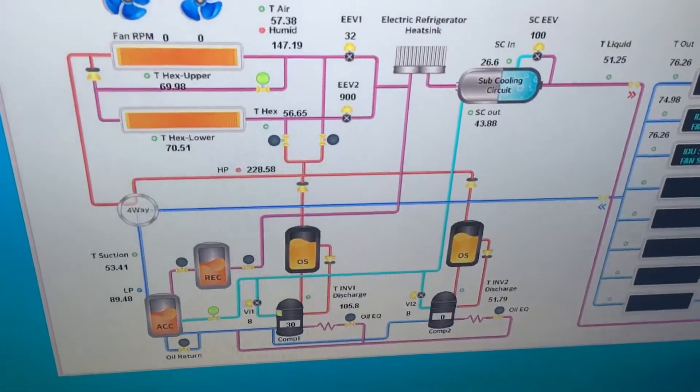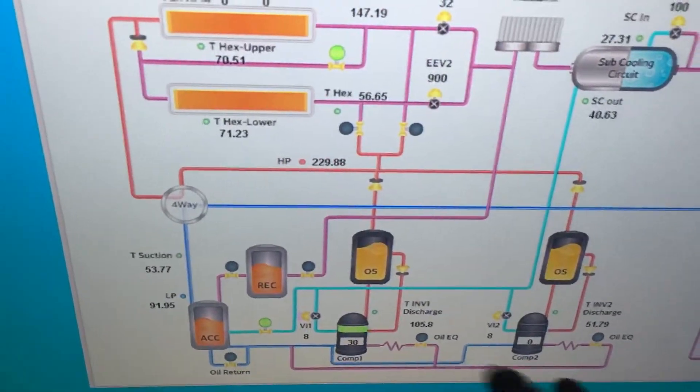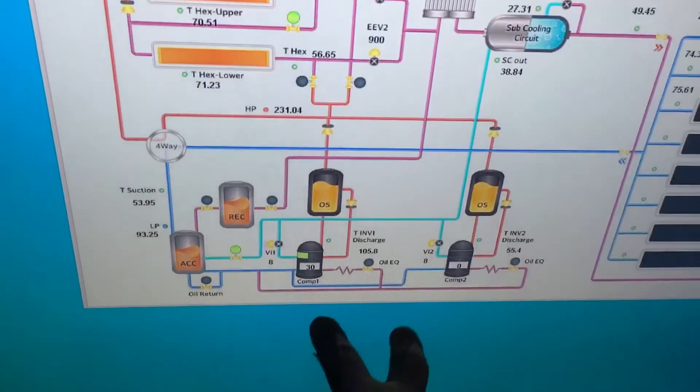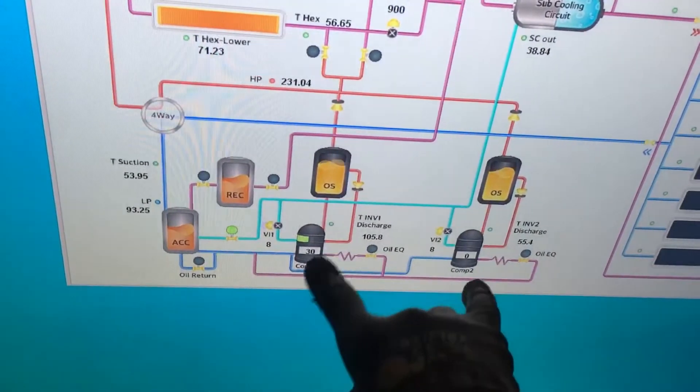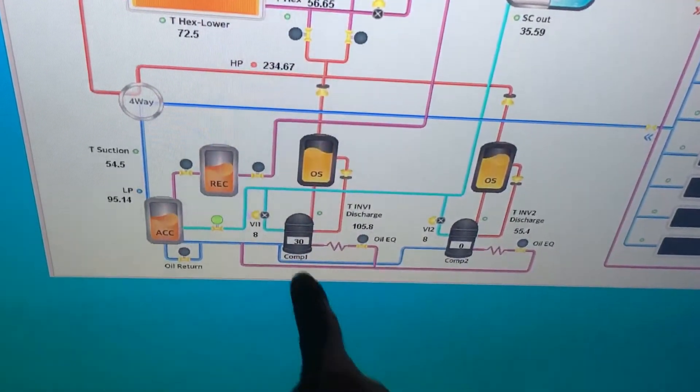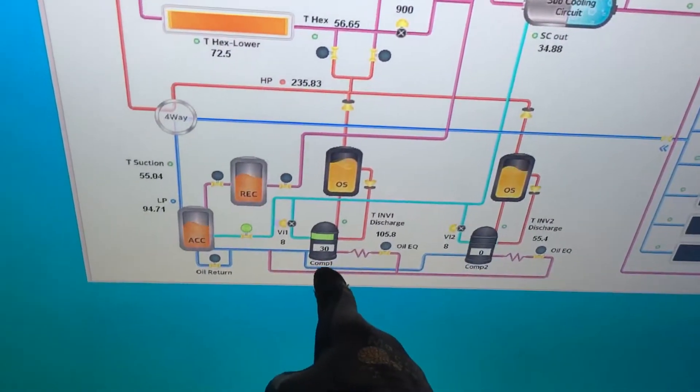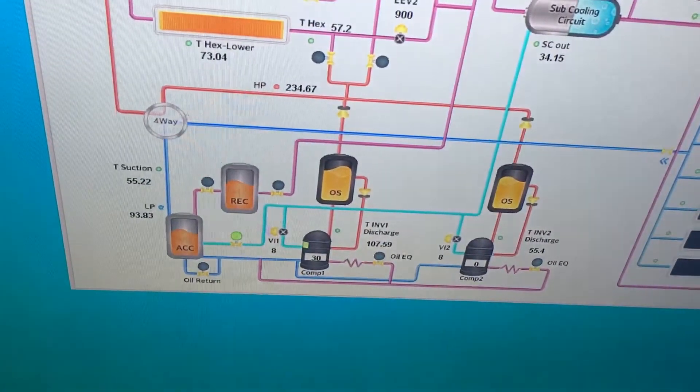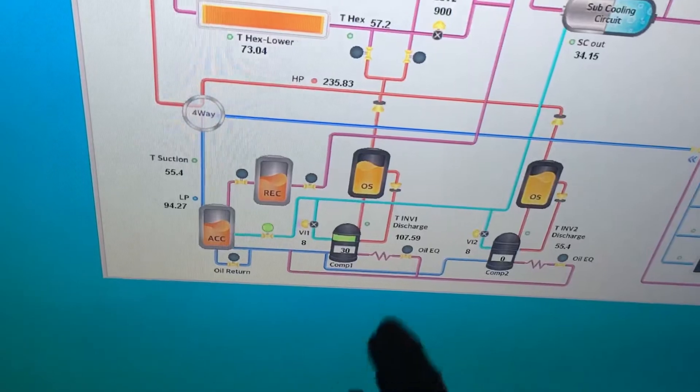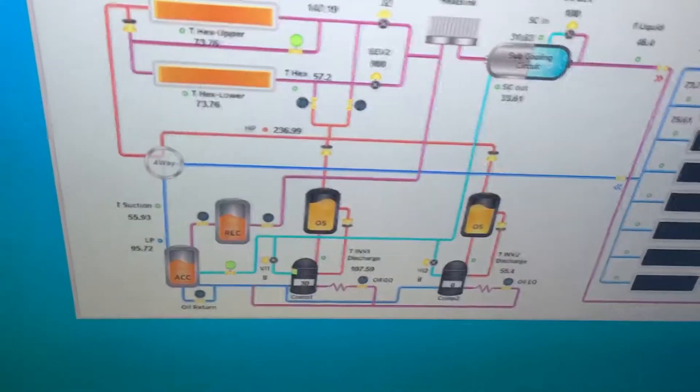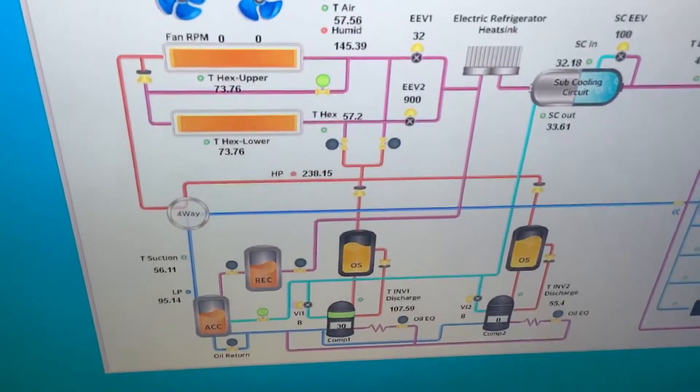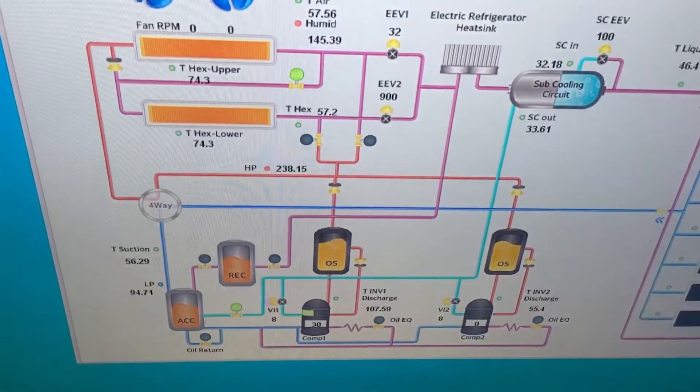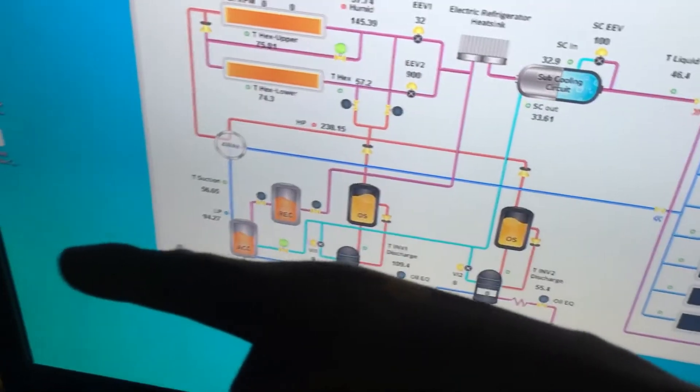So right now the load just went up enough that one of the two compressors in the heat recovery unit up on the roof is only requiring roughly 30 hertz, half the drive of one compressor, to handle that whole load right now. But as the room slowly creeps up and it has more of a demand because we turned off the other system, you'll see this compressor go up.